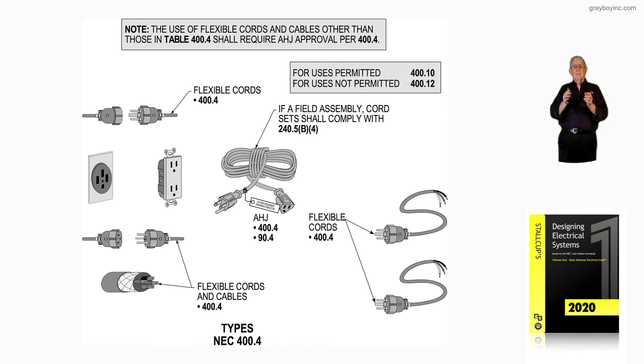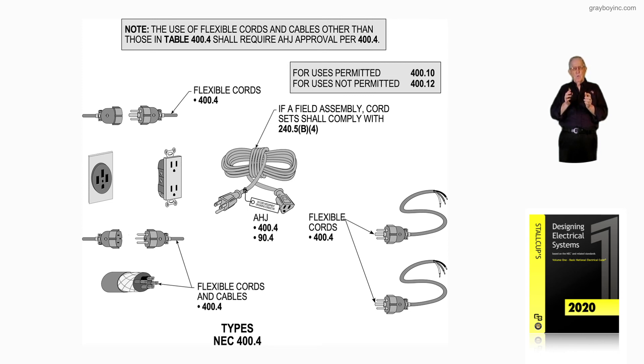So this is a summary of the types of cords that we would want to review in 400.4 to see if they are a listed type outlined there. If not, and we're using something that's not outlined in 400.4, we need to check with the authority having jurisdiction and see if what we're using would be equivalent to or better than what's referenced in 400.4 and table 400.4. And that's what most inspectors are telling me they will go by if they're going to approve it at all.